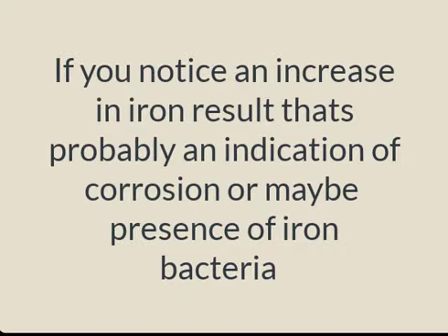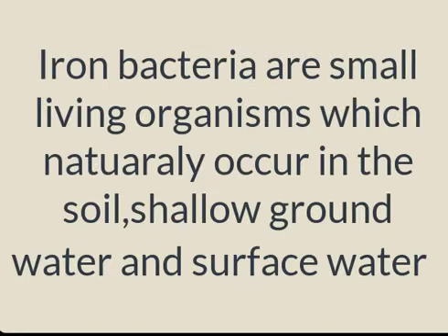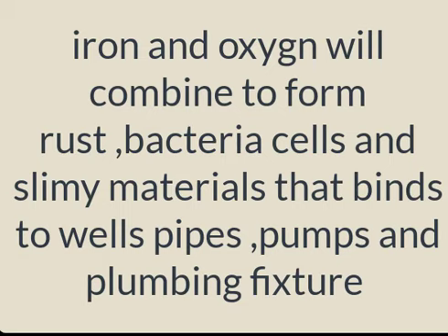If you notice an increase in iron result, that is probably an indication of corrosion or maybe the presence of iron bacteria. Now iron bacteria are small living organisms which naturally occur in the soil, shallow groundwater and surface water. What happens is the iron and oxygen combine together to form rust, bacteria cells and slimy materials that bind to the wells, pipes, pumps and plumbing fixtures.